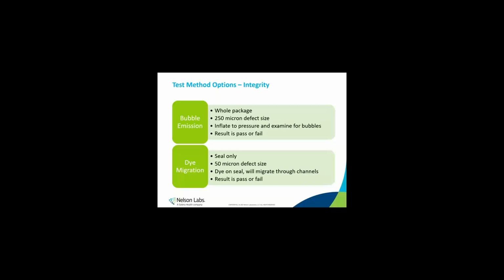Both of these are pass-fail or attribute data tests. As such, the acceptance criteria is normally that they all pass, though theoretically there are some sampling plans that do have allowable failures for very low risk situations. And those usually have very high sample size numbers as well. This will all depend on how you write your sample size justification. The integrity component is perhaps the most vital one, and it would be very hard to justify less than 100% pass rate for a sterile package.